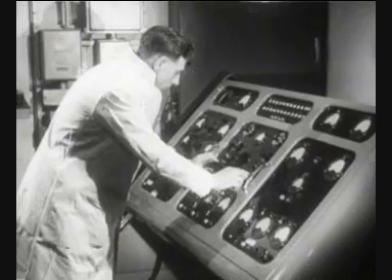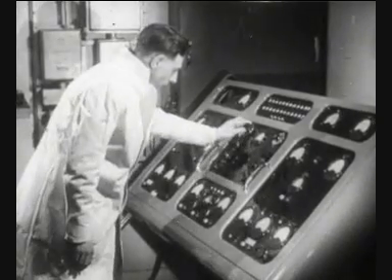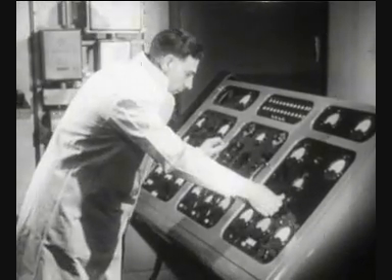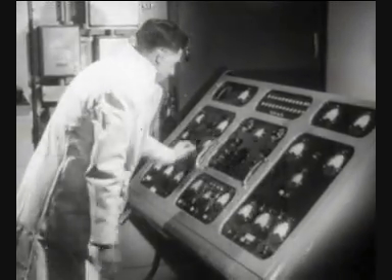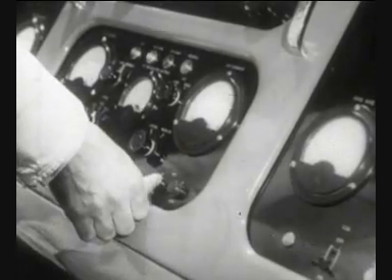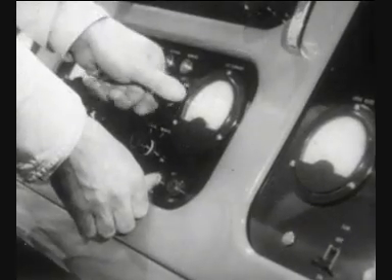The X-ray technician brings the machine into correct running form on this main control panel. Here, he controls the voltages, the modulator waveforms and the focusing of the electron beam in the accelerator.